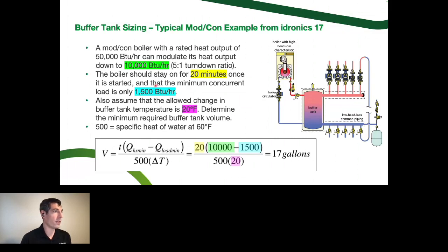We need to know what is the smallest load. Is there like a single towel warmer radiator in a guest bathroom or something like that? What is the minimum load that could be on that would be enough to cool down the buffer tank and fire the boiler? And then we need to know how cold can we let this buffer tank go? Can we charge this up to 180 degrees in the morning and let it fall all the way down to 105 degrees throughout the day?